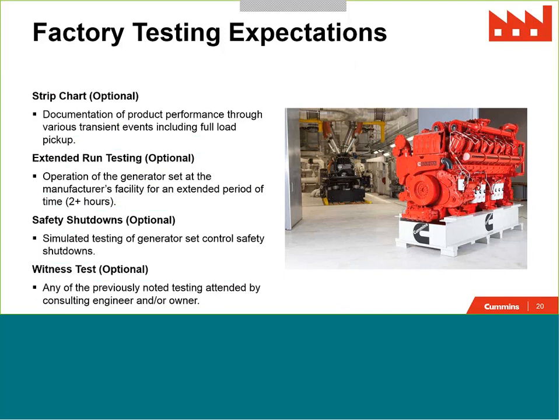Demonstration of the safety shutdowns is also a common test. However, it's important to note that most generator set manufacturers simulate the safety shutdowns, and what I mean by that is if this shutdown that is requested to be demonstrated is excessive oil pressure or low oil pressure, the manufacturer isn't going to cut an oil pressure line on their live product to demonstrate that the safety shutdown works as intended. Instead, what's going to happen is a control system is going to be used to simulate a loss of oil pressure to the generator set control, where you will see it appropriately shut down as needed by the generator set manufacturer.